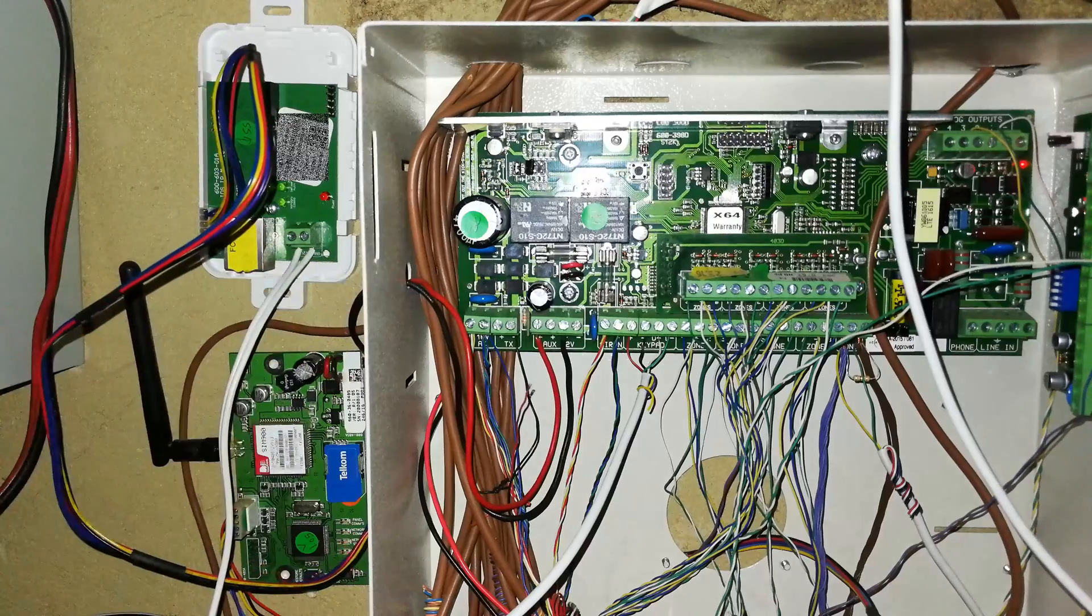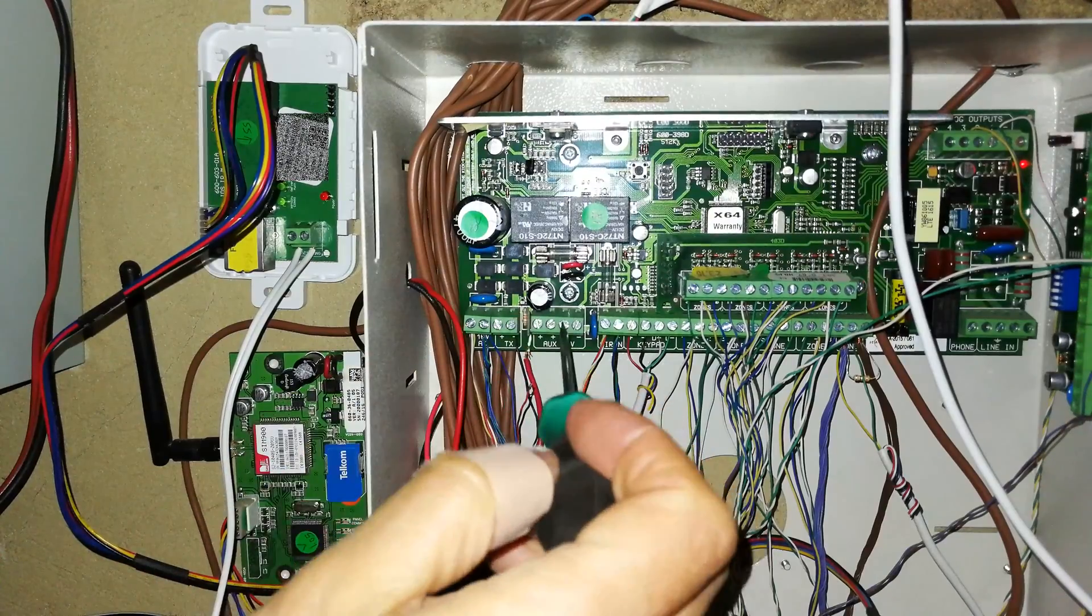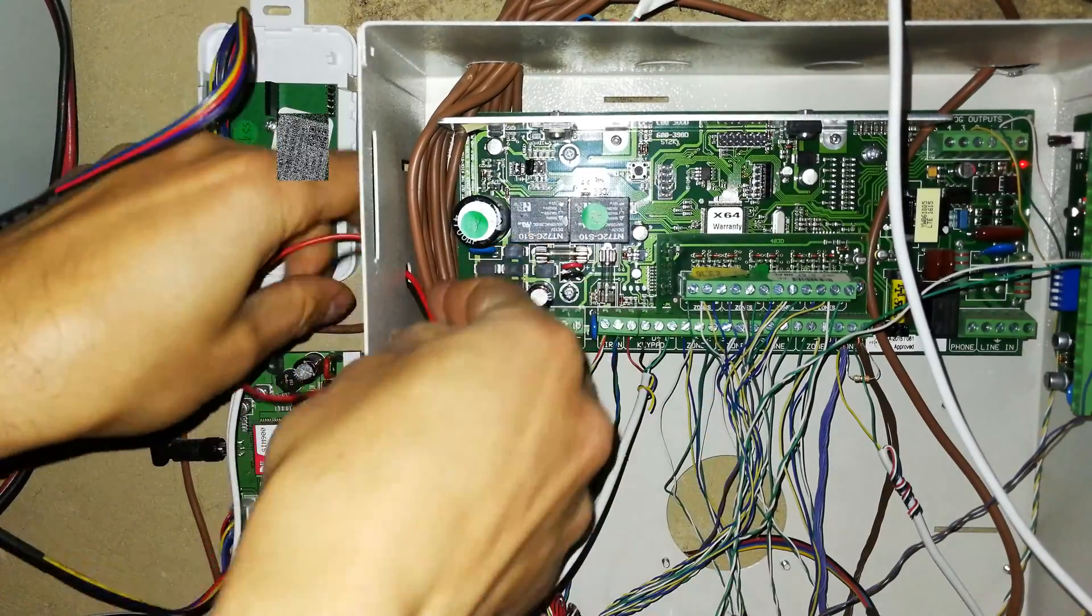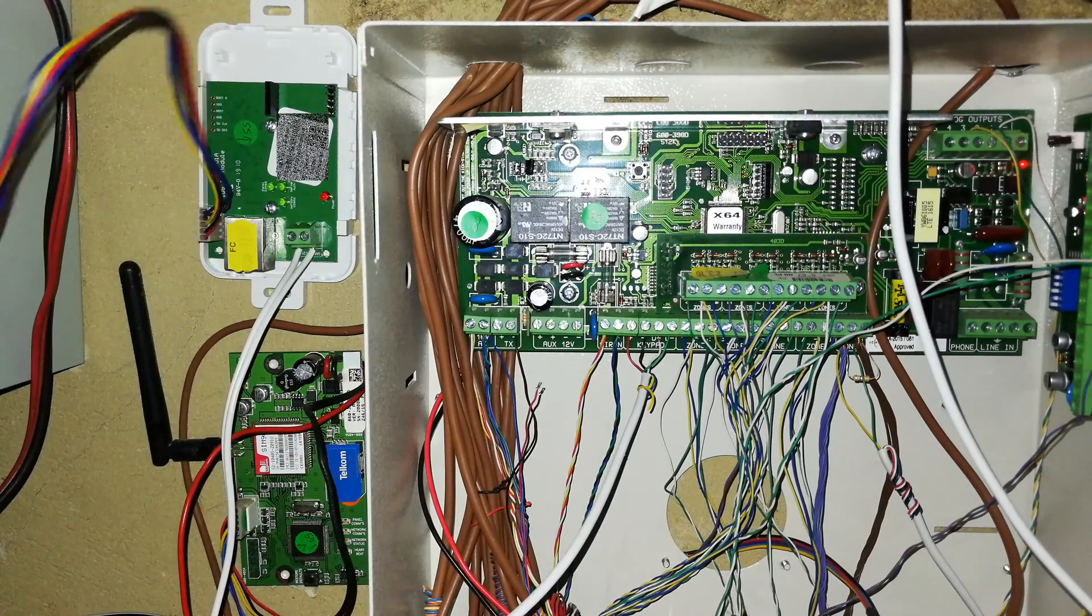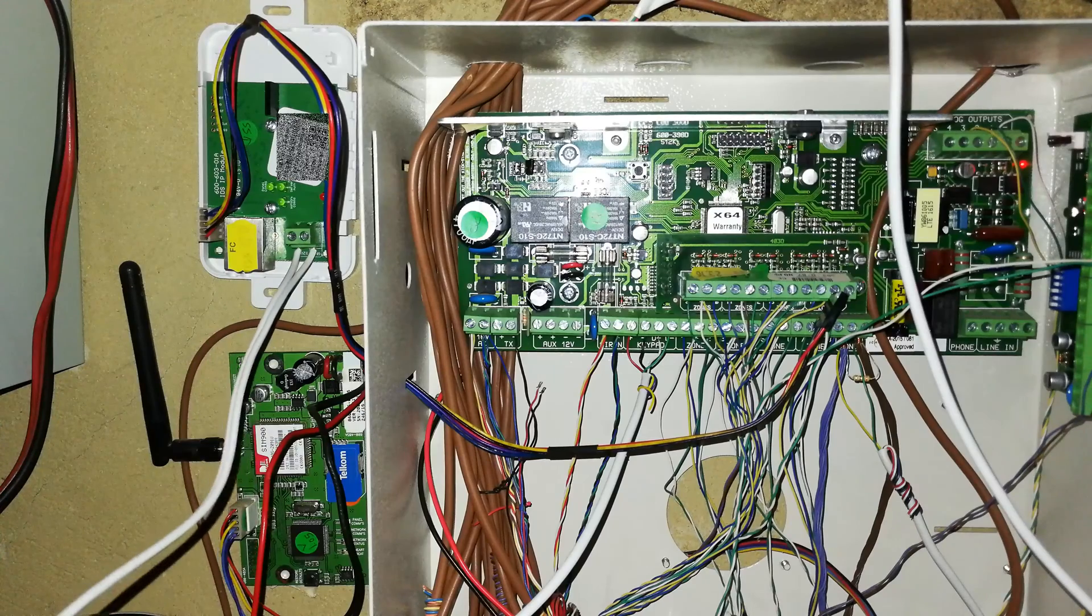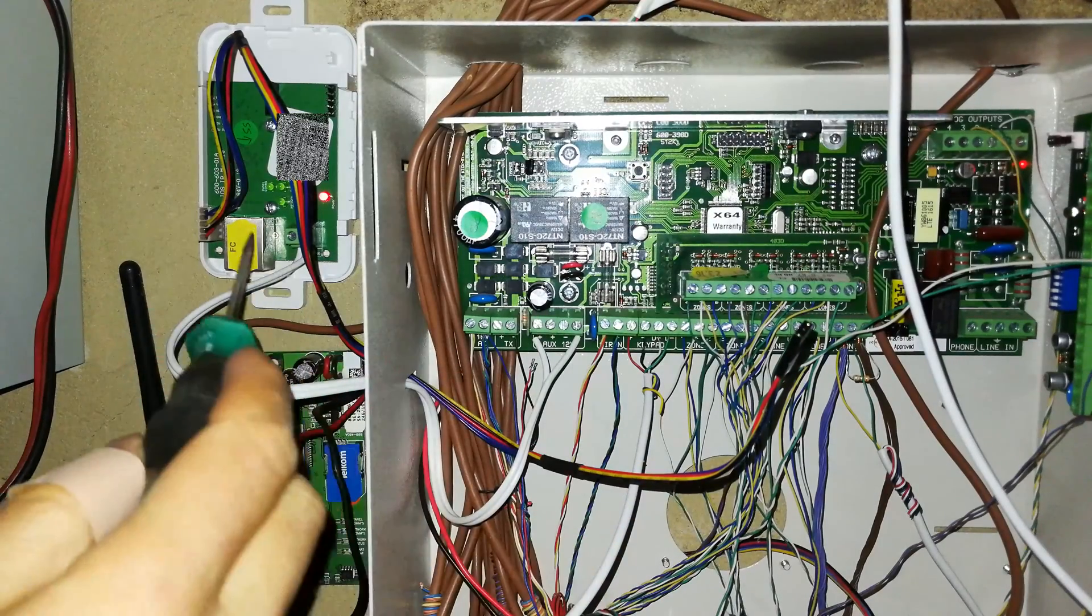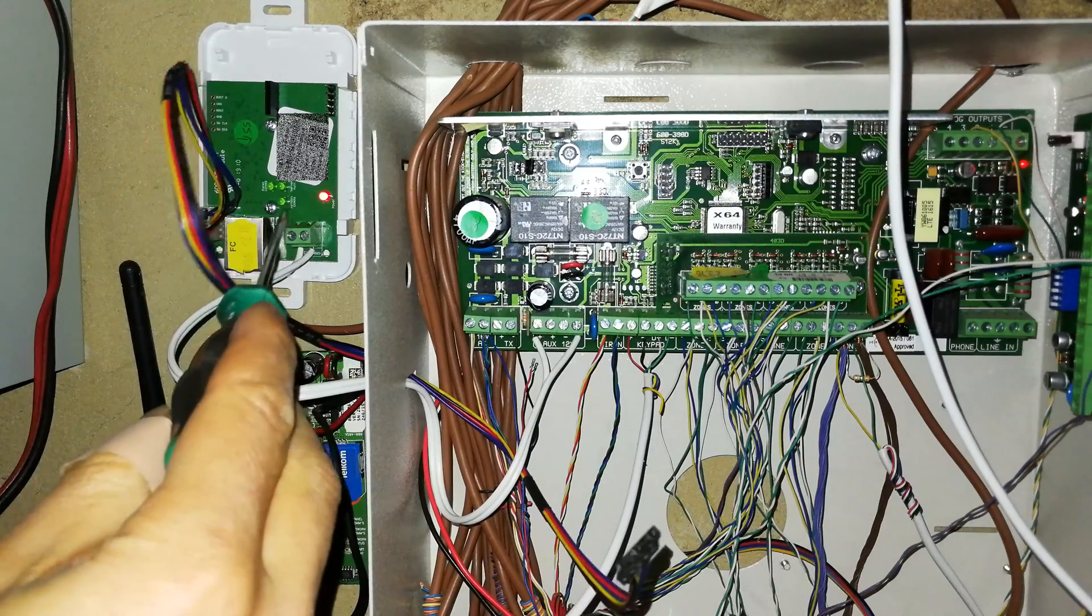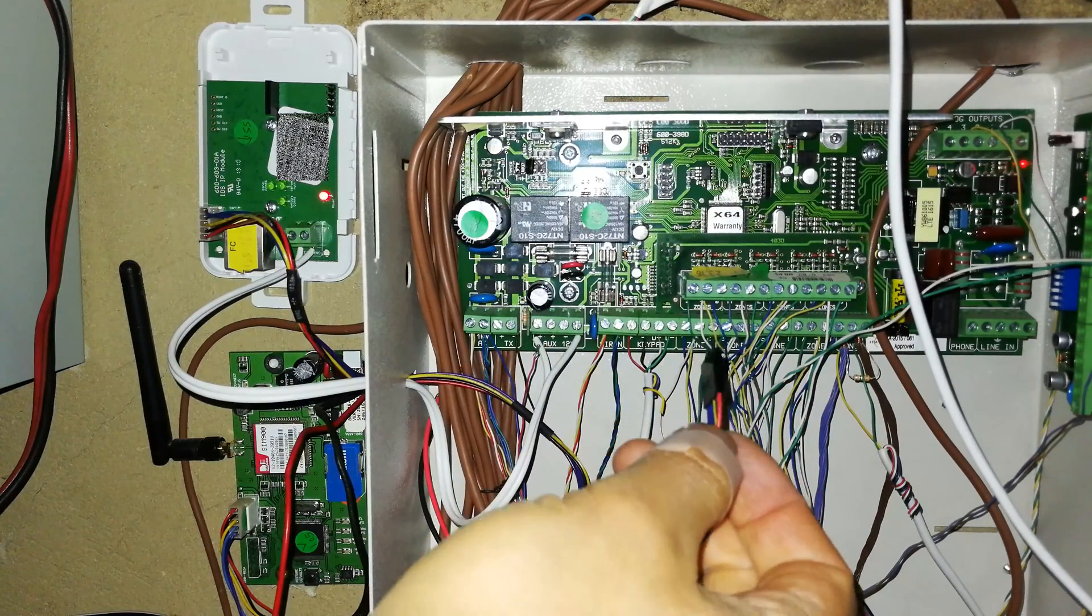Now I'm going to disconnect the 12 volt and ground of the X SMS communicator, so that will power down now. I'm going to feed these wires, the new wires, the serial cable plus the positive and negative of the IP Connect. There's positive and negative, and you can see the status coming up there, there's some flashing lights. I'm sure these light sequences mean something. Now I'm going to plug this in to the panel, red at the top.